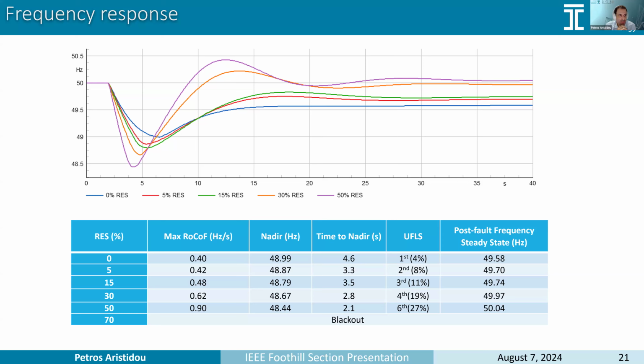The supercapacitor can provide a very fast response in the beginning, but again, if you don't move to grid forming technologies that can respond almost instantaneously, you will have measurement issues. For example, to measure the frequency, you usually need at least 3 cycles to get a good measurement, because 1 cycle is not enough to give you an error-free measurement. So usually you need 3 to 5 cycles. And in Europe, that means 60 to 100 milliseconds already to get a measure of the frequency.